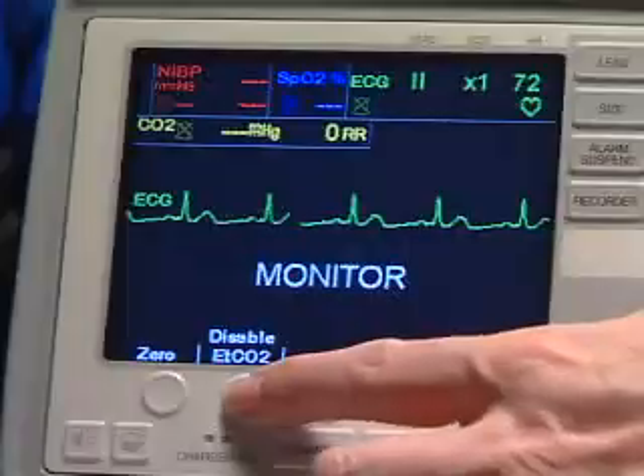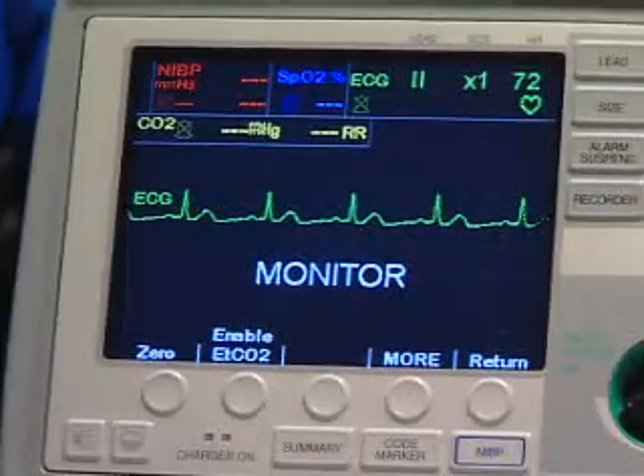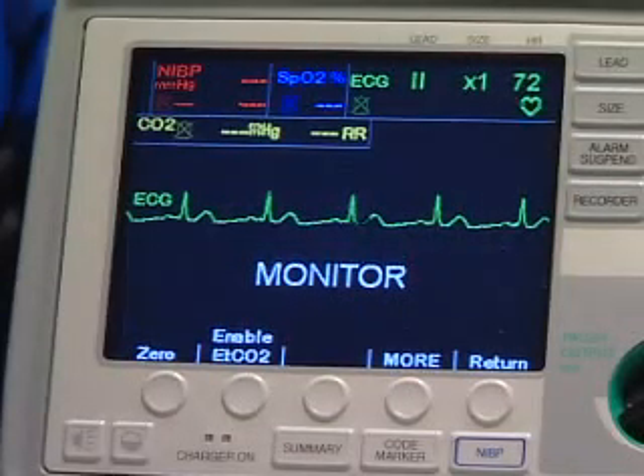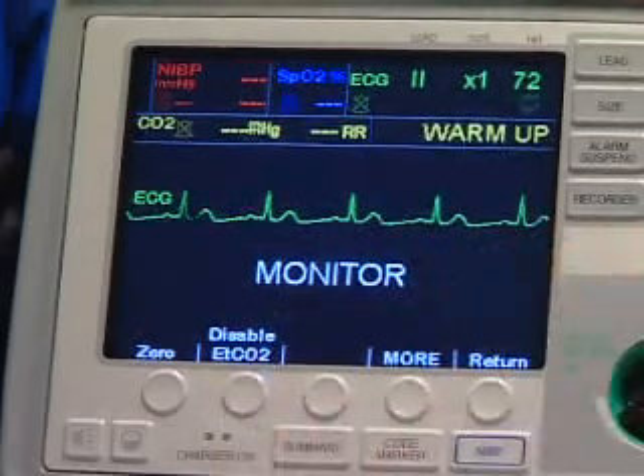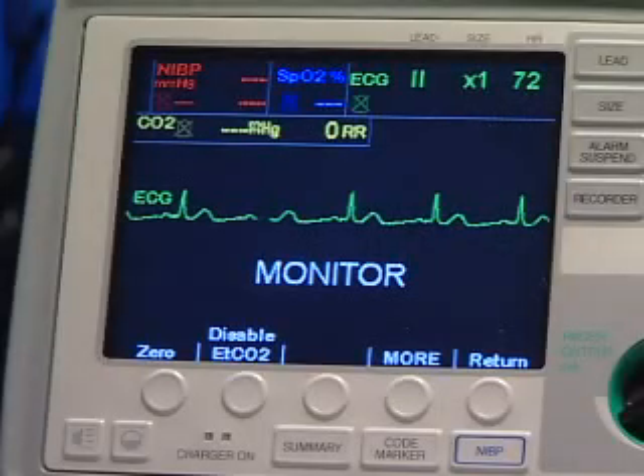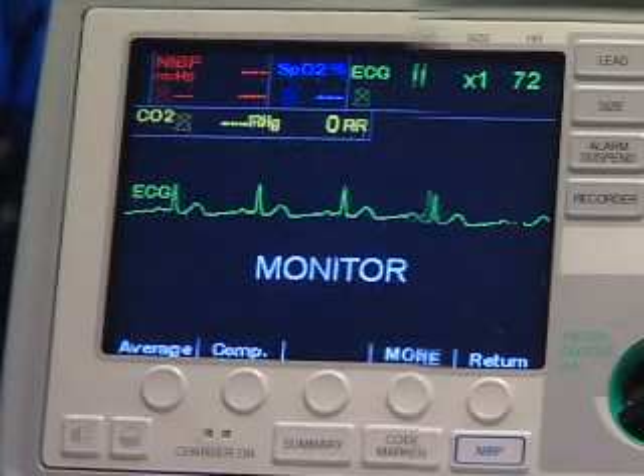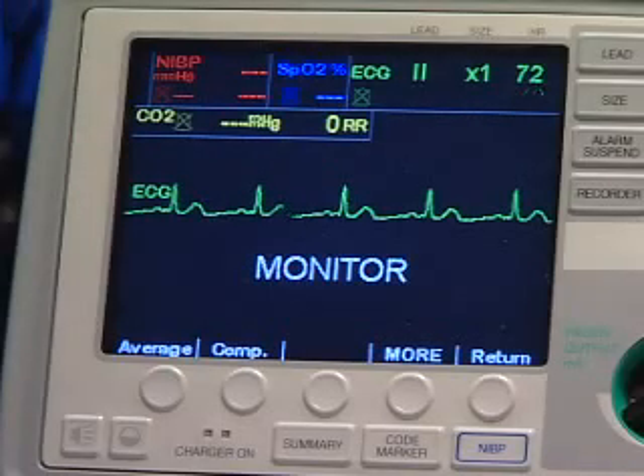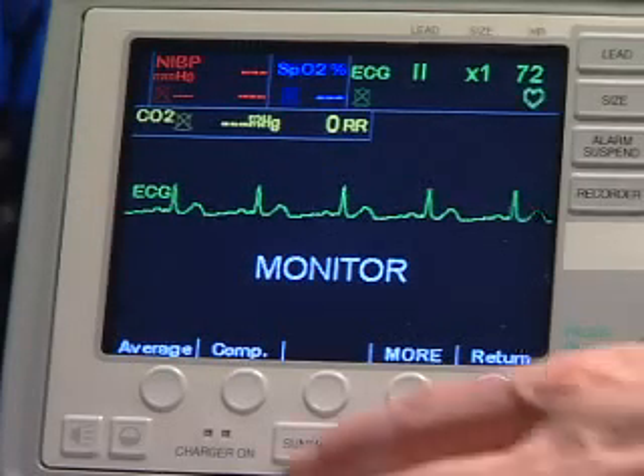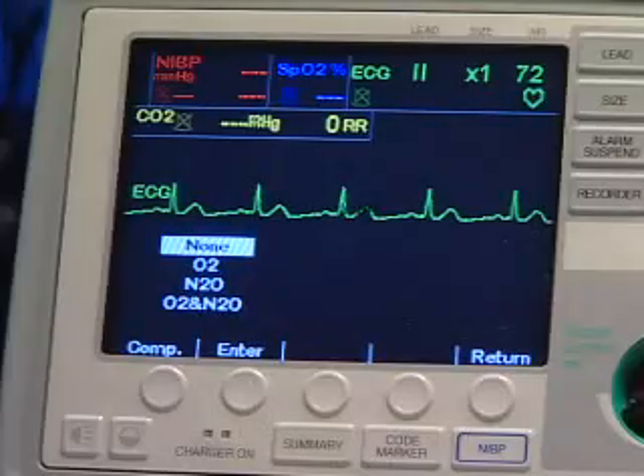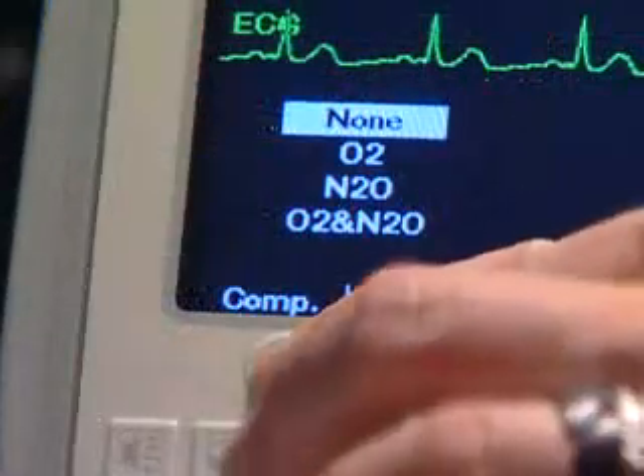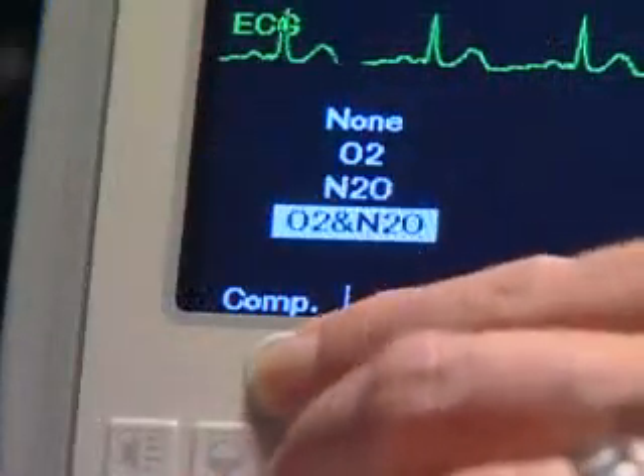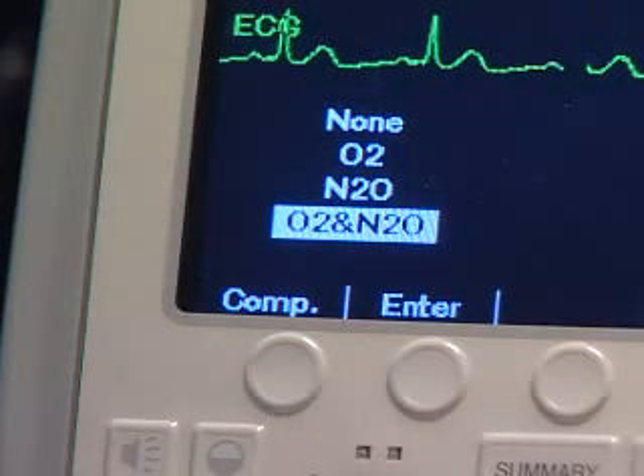Pressing the Disable ETCO2 soft key puts the sensor into the power saving mode. Pressing the Enable ETCO2 soft key takes the sensor out of sleep mode and turns the heater on for normal operation. The Compensation soft key provides compensation for elevated levels of oxygen, 60% or greater, and for the presence of nitrous oxide, or both. Pressing the Comp soft key scrolls the highlight bar through the different types of compensation available, either none, O2, N2O, or both O2 and N2O.